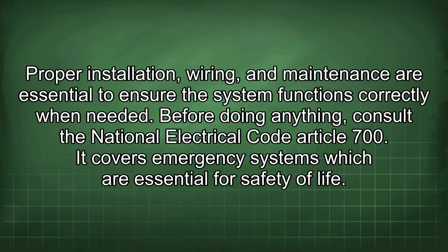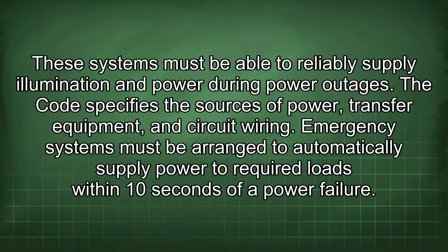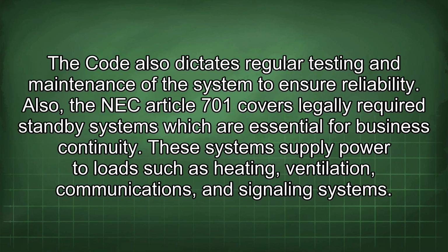Before doing anything, consult the National Electrical Code Article 700. It covers emergency systems which are essential for safety of life. These systems must be able to reliably supply illumination and power during power outages. The code specifies the sources of power, transfer equipment, and circuit wiring. Emergency systems must be arranged to automatically supply power to required loads within 10 seconds of a power failure. The code also dictates regular testing and maintenance of the system to ensure reliability.